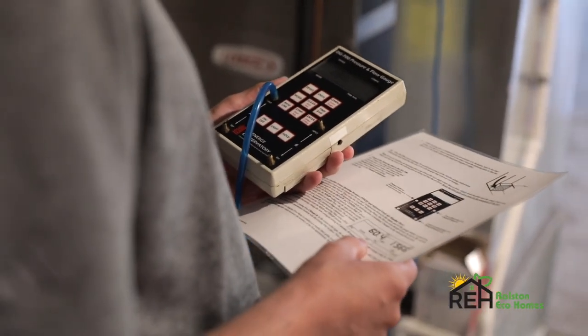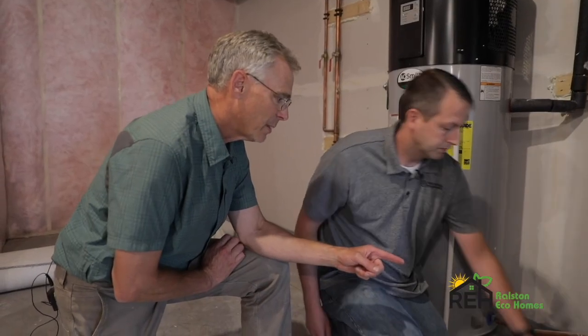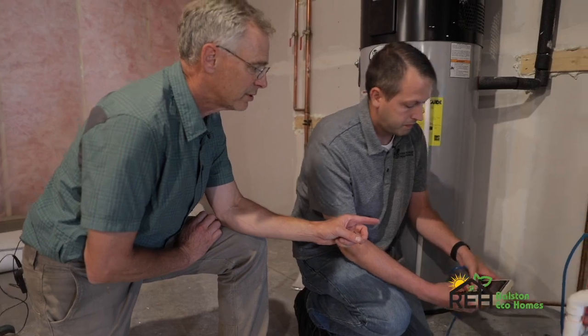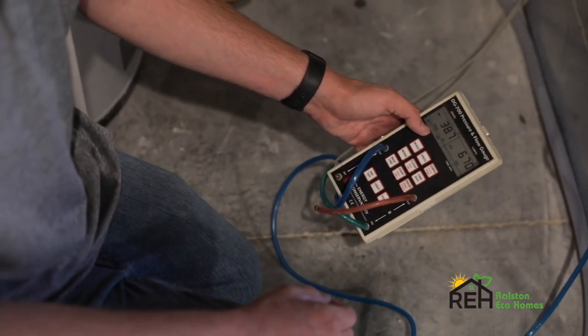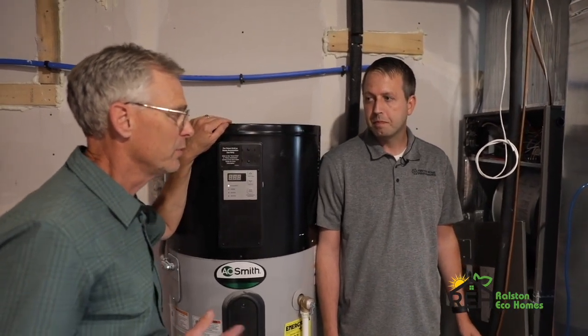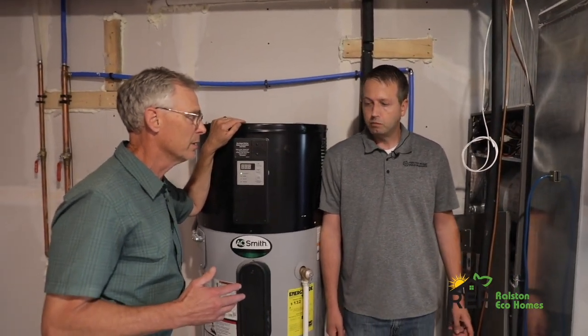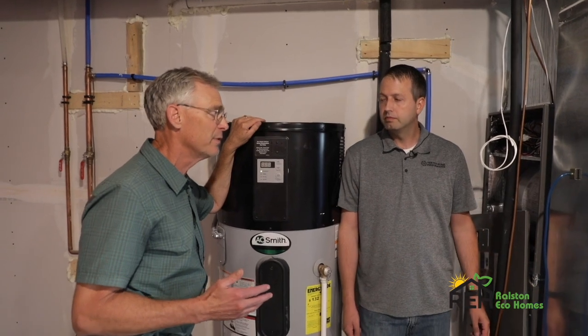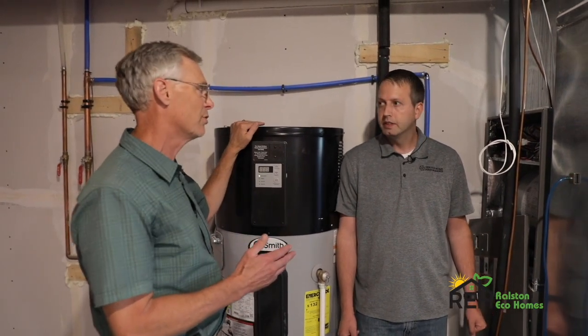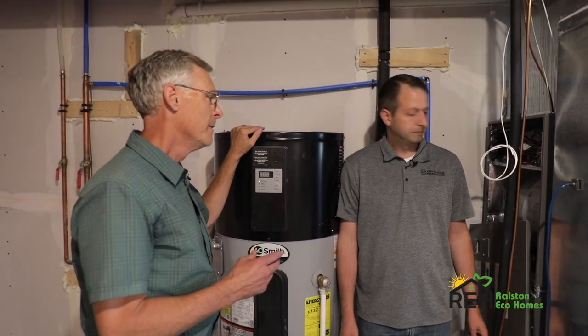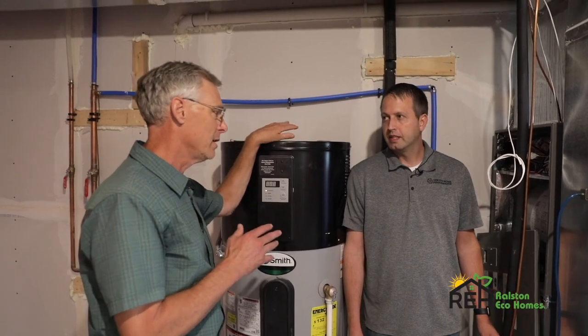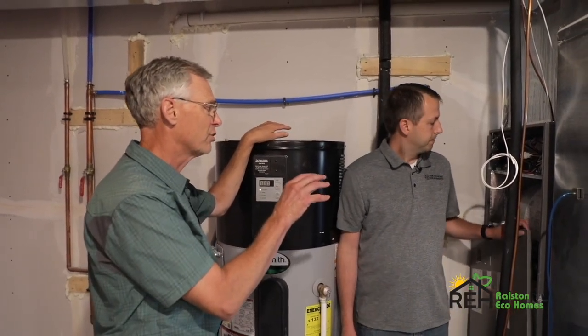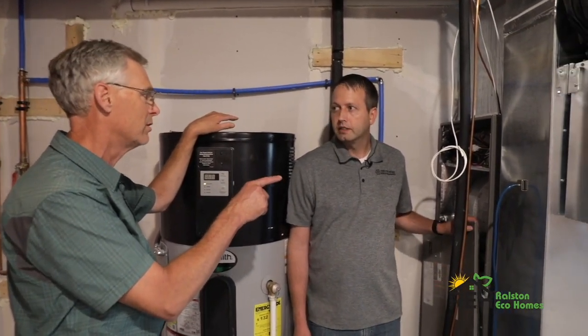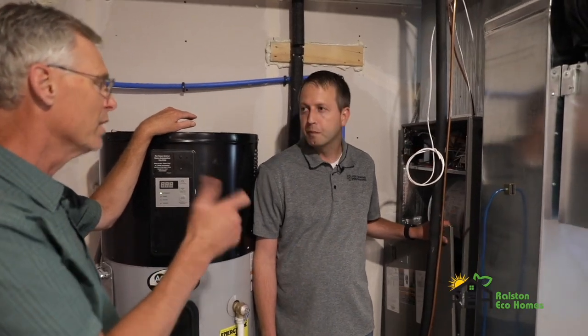Correct. Okay, so what you're telling me then is the amount of flow through the system is 670 or something. So what we've talked about so far is that 670 might be a little bit low, that the unit should be more in the 700, 750 range per the manufacturer's recommendations. And then the way you would adjust that is by changing the circuit, the way that the wires are connected to the fan, so that it runs at a higher speed.